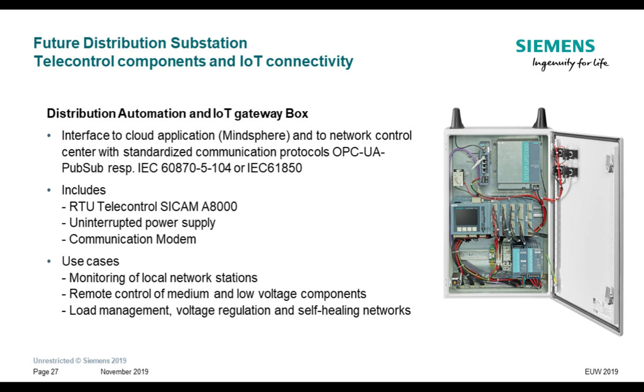This connectivity to the different devices is done via predefined connectors and plugs, so it's quite easy to install, to update, and to always have the most recent installation in place for the future distribution substation. That is quite important. The communication from these devices is via Modbus RTU or other protocols inside the station.